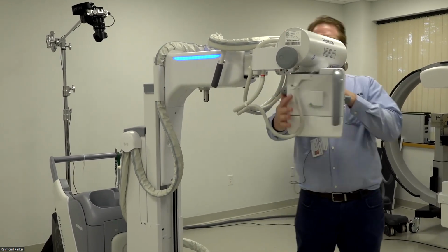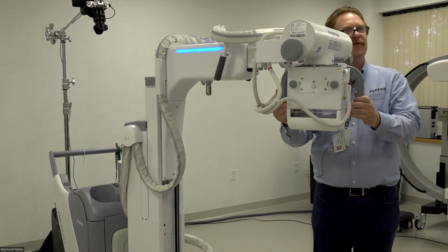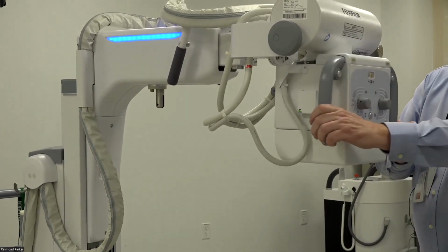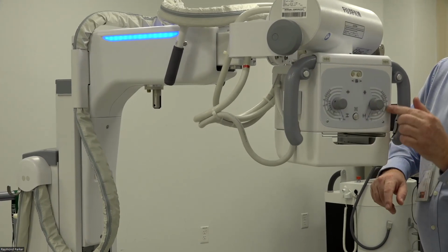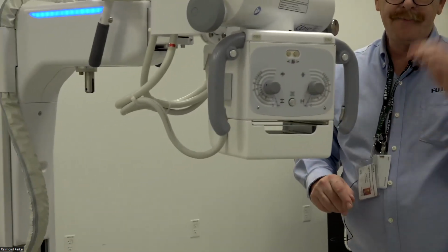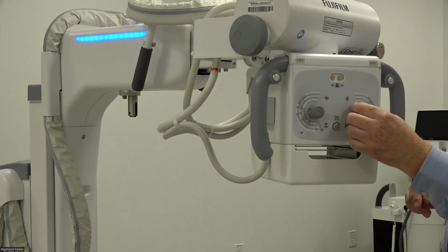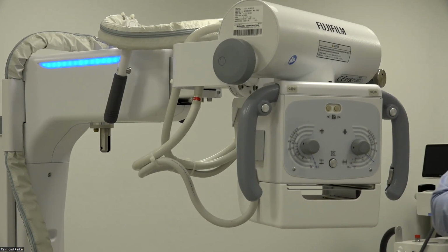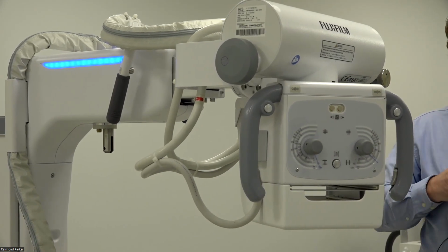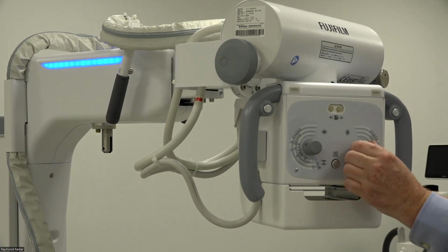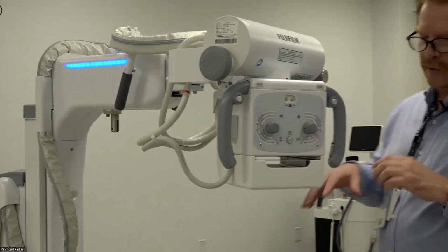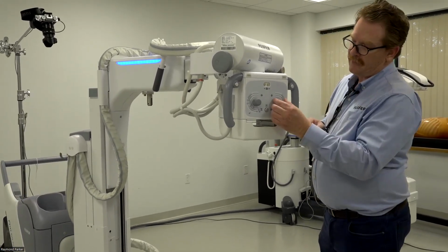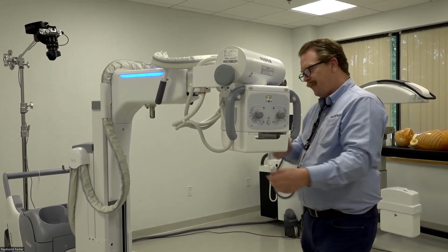One of the nicest features of the portable Go Plus is that it's got dual collimator controls on the front and back of the collimator head. The face has actual measurements that are accurate. When doing virtual grid images on bariatric or large patients, or any virtual grid image, you can trust these measurements for field size corresponding to the actual film size, using these and an accurate SID measurement.